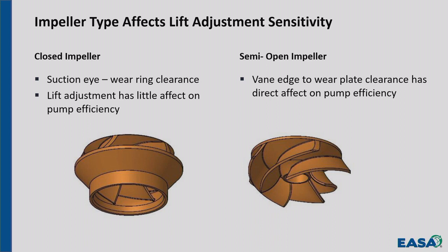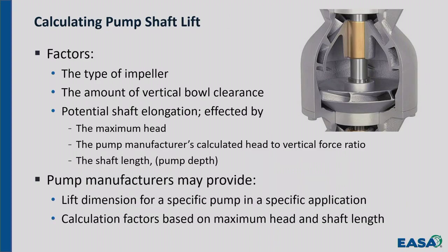If it's a semi-open impeller, you're going to adjust the load when you adjust that clearance. And you'll also be affecting the efficiency of the pump. Okay? So the type of the impeller makes a difference. Just to cut this short, you want to know what the maximum amount of clearance you have. Sometimes that means just raising the shaft up until you can rub on the top. And, of course, you know where it was on the bottom. Then you know the full range that you've got.